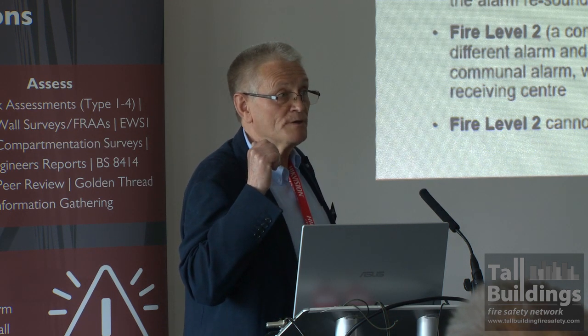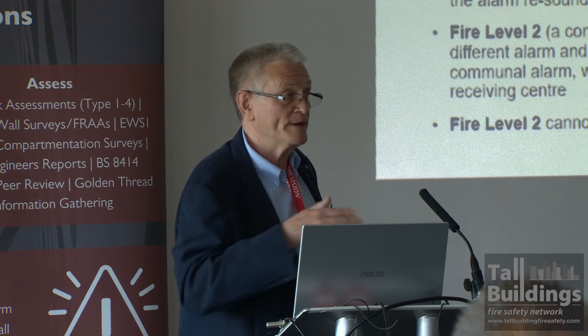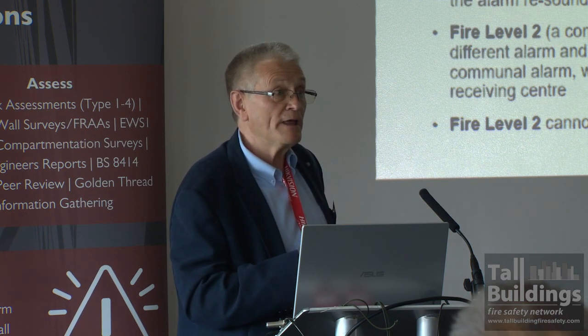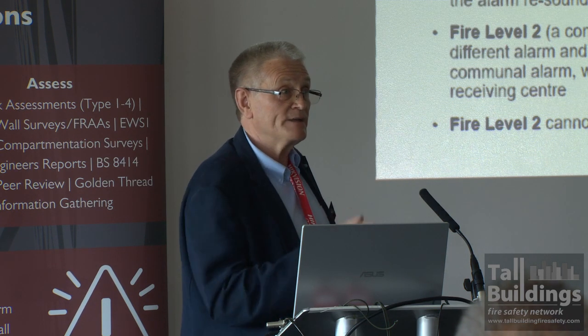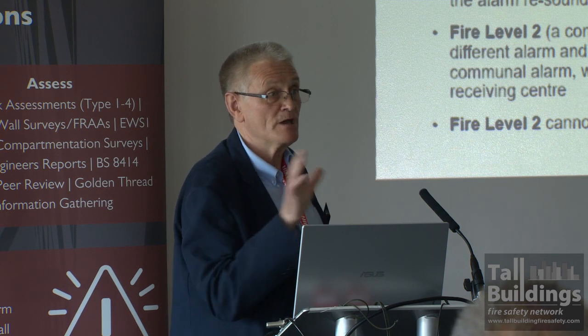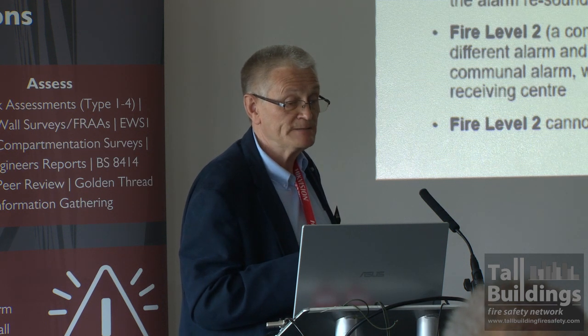and the user, the occupant, can press the hush button and it'll shut up for 2 minutes while they go and open the window and waft. And if they haven't wafted enough, after 2 minutes, it will probably go off again, and they can hush it again. Now, these events are being logged on the cloud, but they're not setting off the communal system. So it's no different, really, than your standard grade D system at that point.